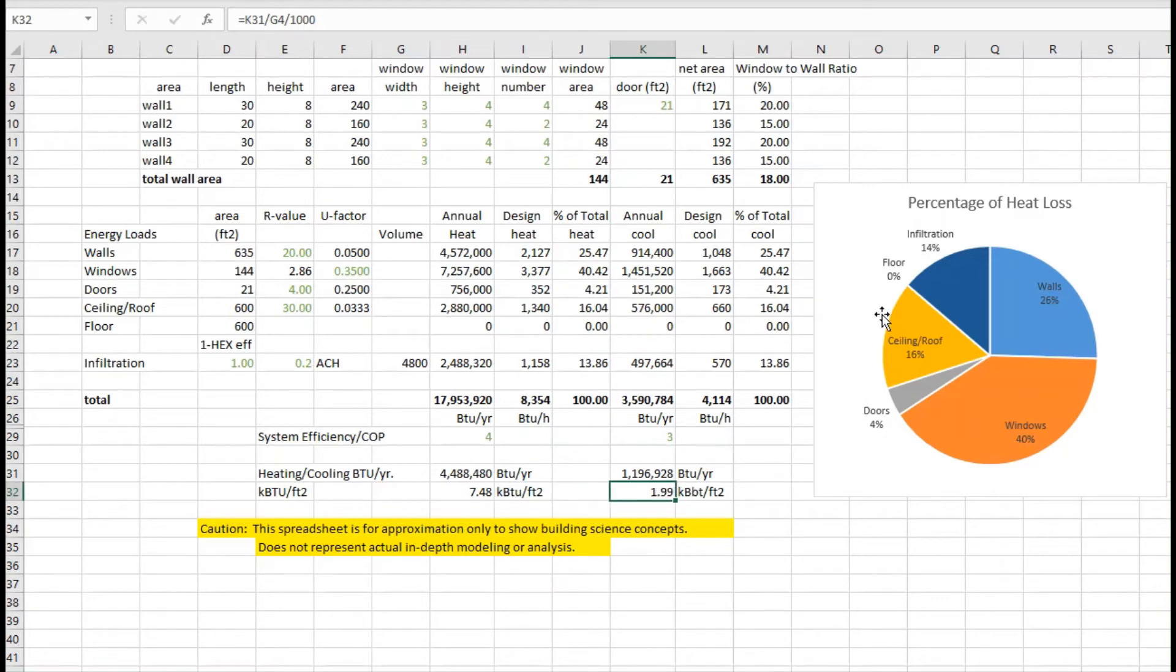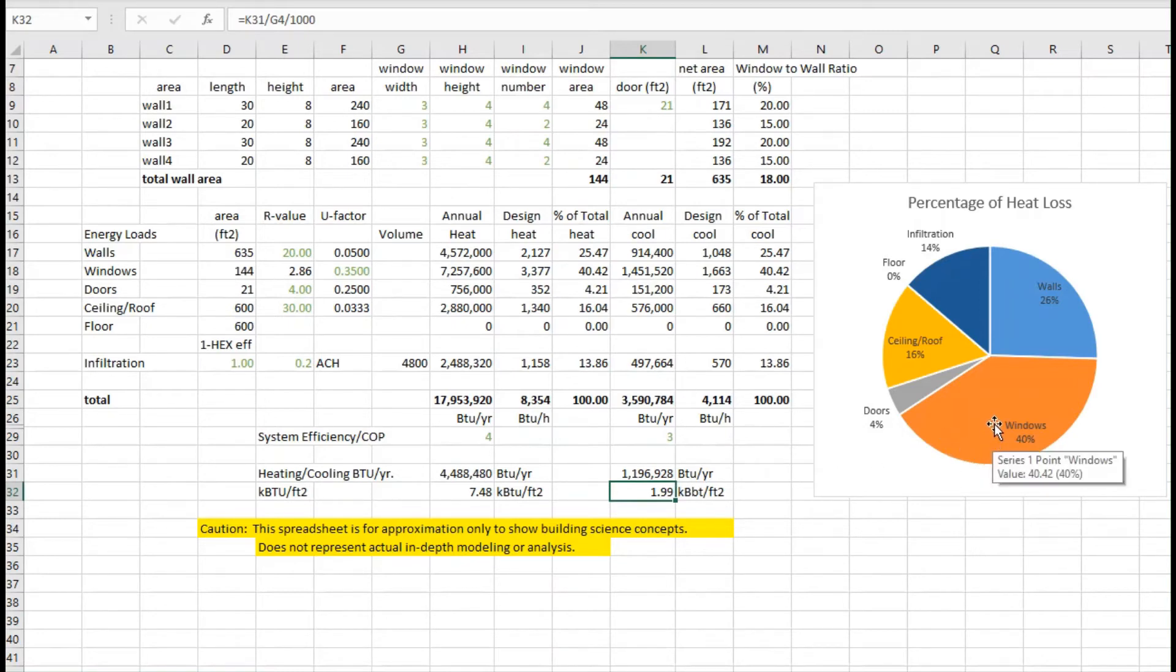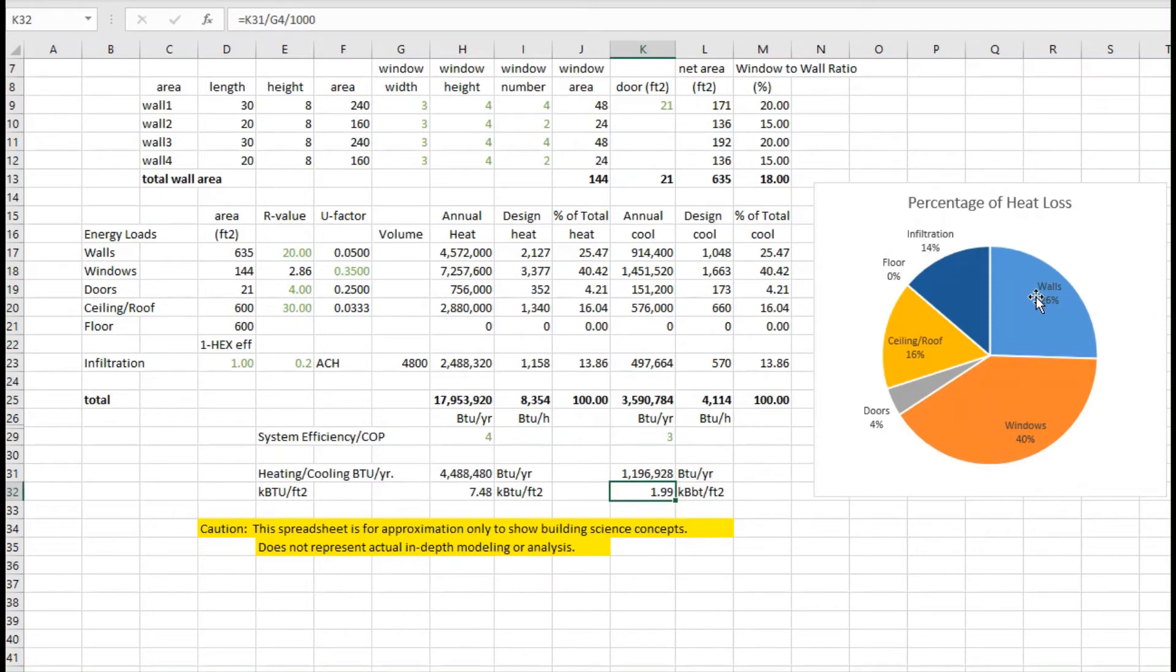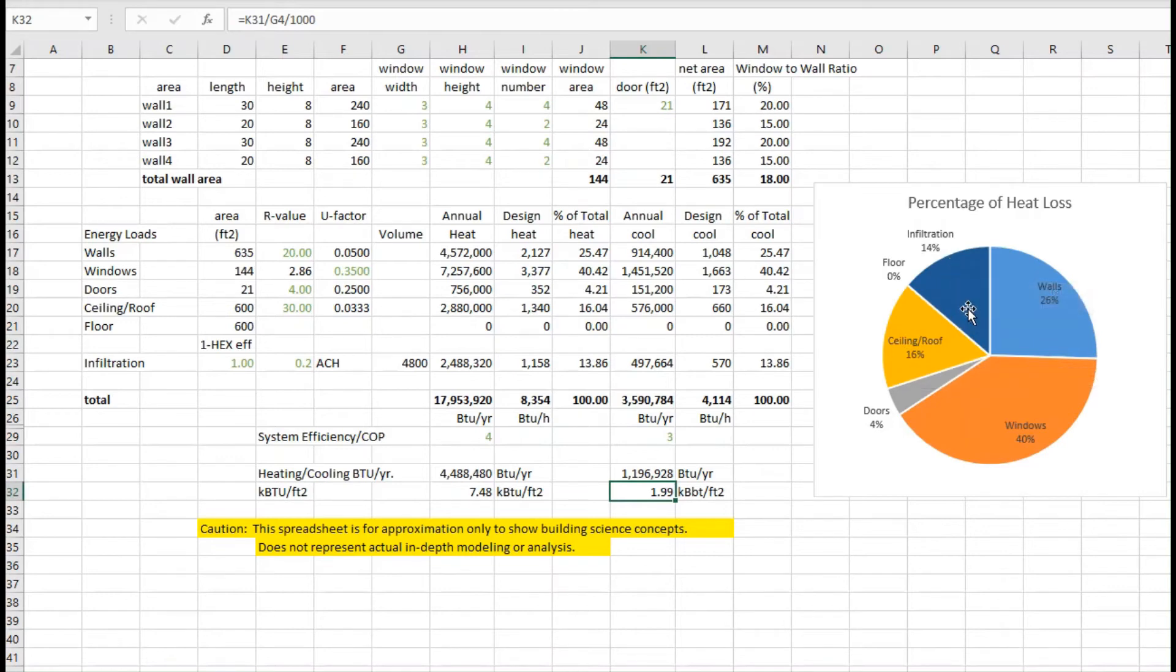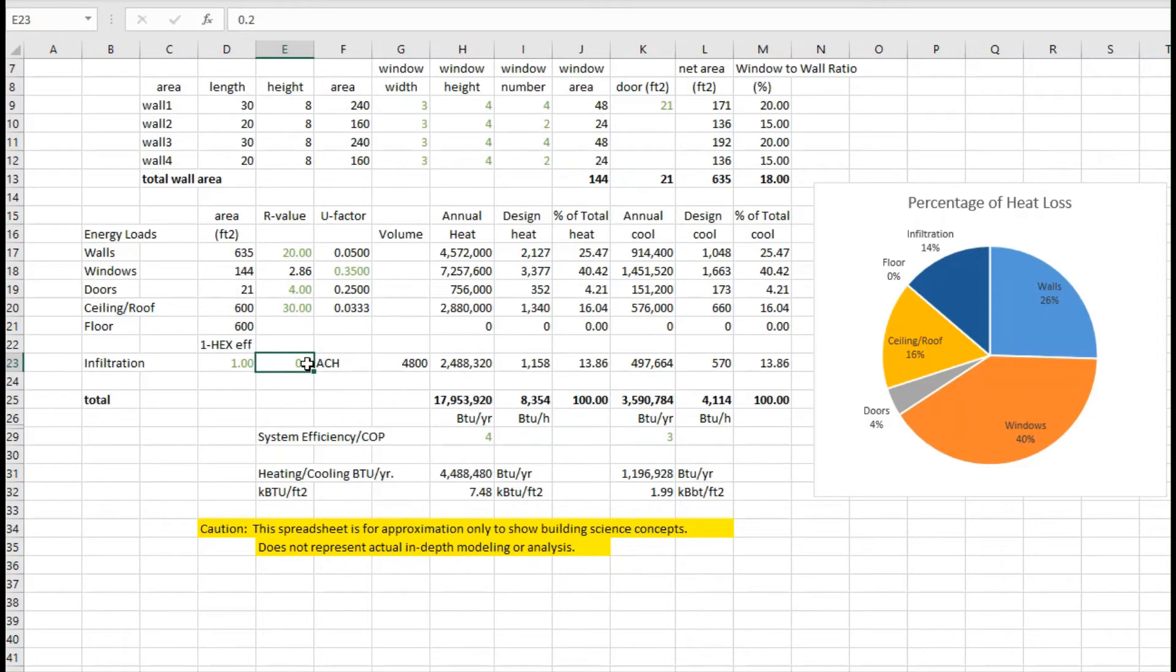Now looking at that distribution of where that energy is going, you can see in this house it's really dominated by the windows and the walls, and then next the ceiling roof is next, followed by infiltration. Just as a note, this infiltration is pretty tight for especially a building of this size, and we'll address some of the infiltration concerns in another episode.